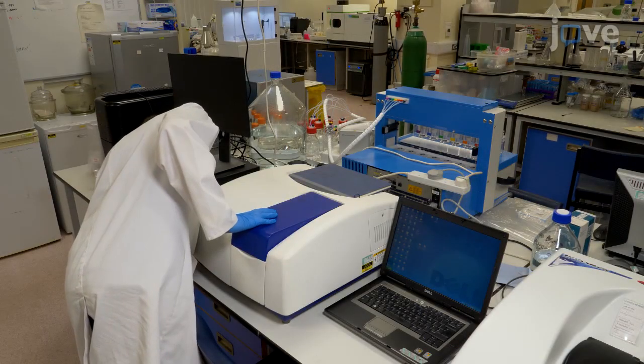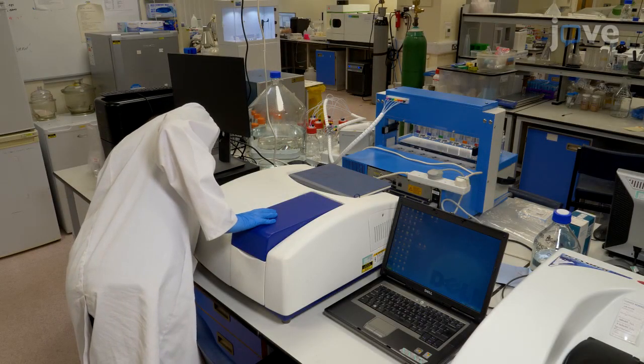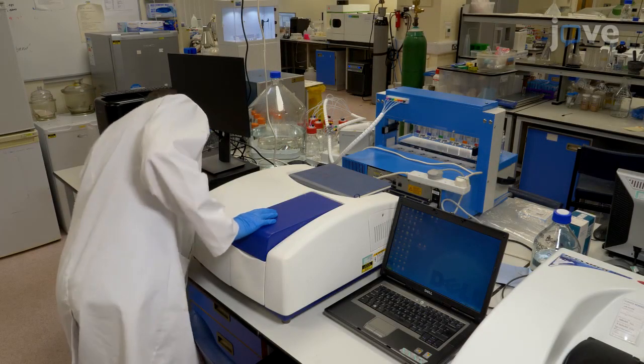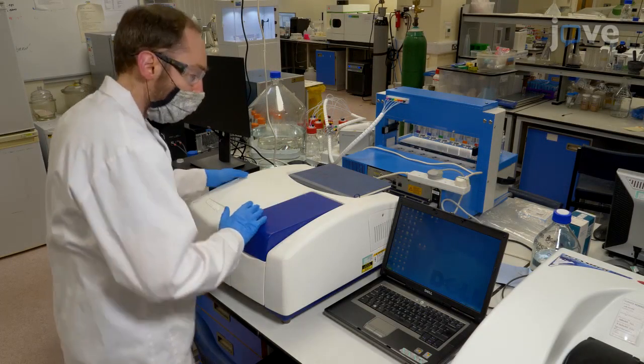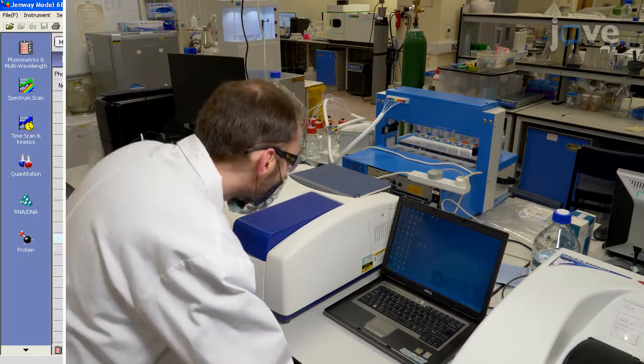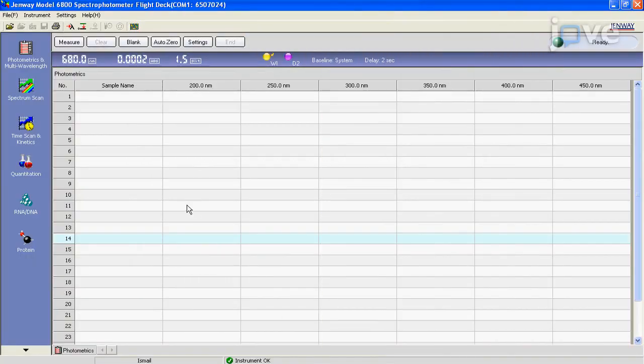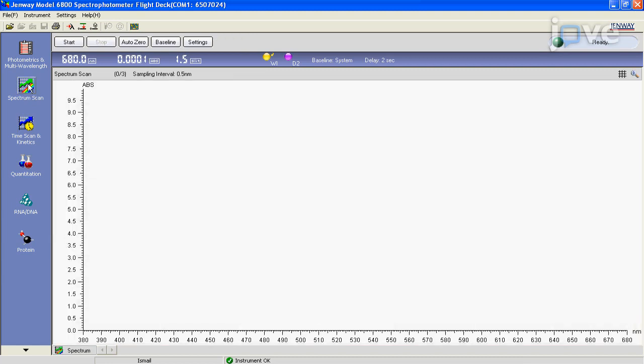Turn on the UV-VIS spectrometer for at least 20 minutes to allow the lamp to heat up. Load the software and select connect the instrument. Select the option spectrum scan from the mode window which displays the operating modes.